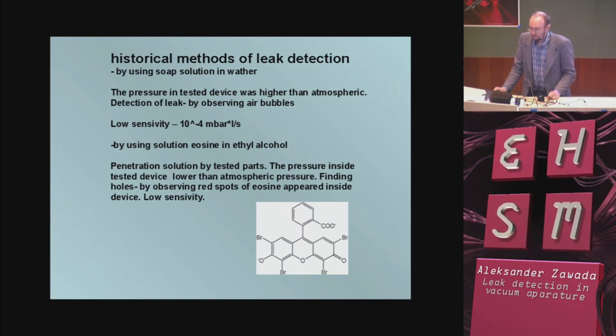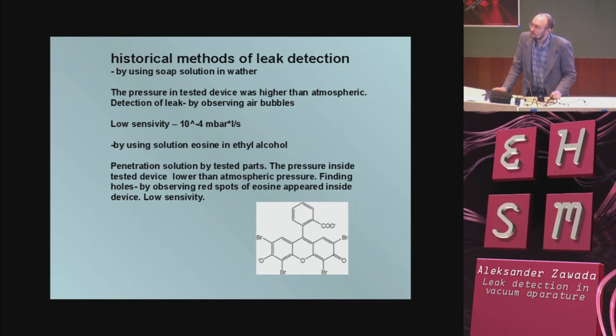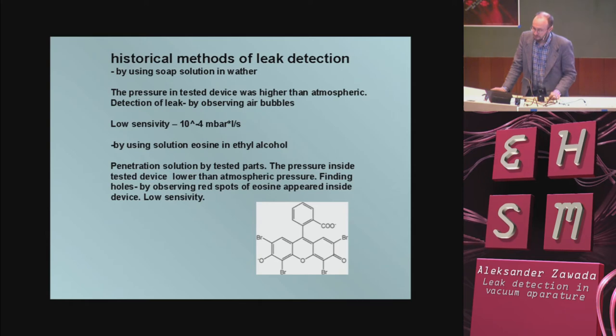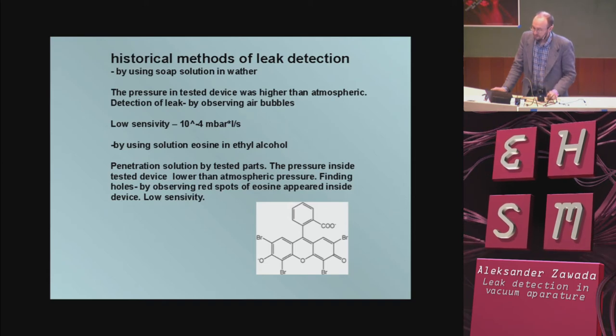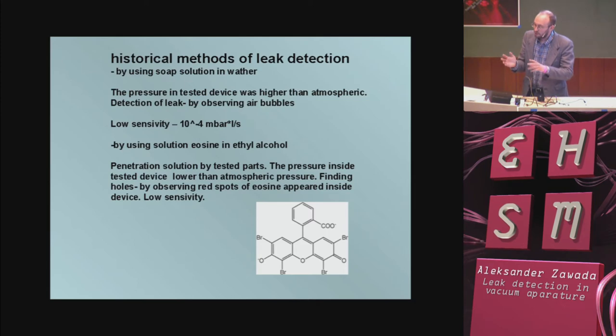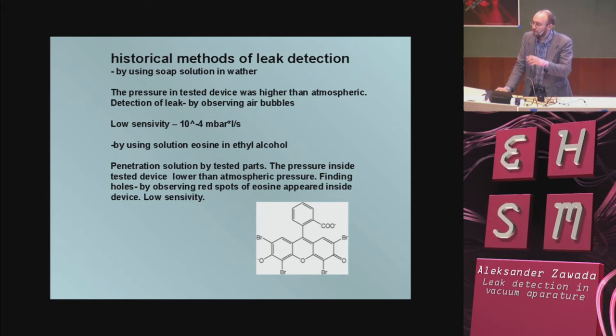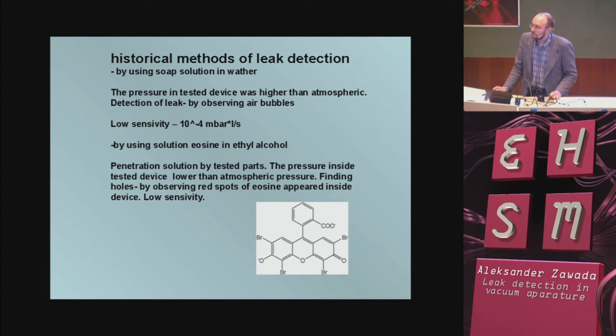Another method: we can use an eosine solution, which was very popular in the USSR. The leaking part is coated with a liquid — a solution of eosine in ethyl alcohol. During penetration of the solution into the tested part, you can observe red spots inside the apparatus. In this method, the pressure should be lower than atmospheric pressure inside the tested apparatus. The sensitivity is similar to the soap solution method.